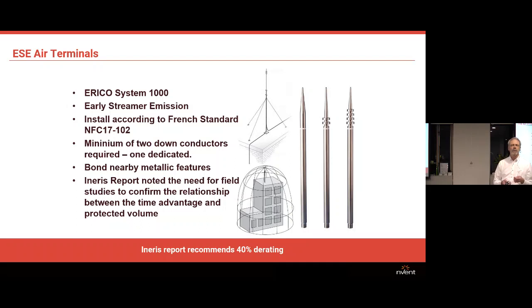But the French government had a lot of these on their building, and they noticed that they were getting bypassed and getting a lot of strikes on their buildings. So they instigated a report called the INERIS report, which found that indeed there were a lot of misses, and this lightning protection method wasn't as reliable as it should be. So they recommended that a proper study be made into reviewing the whole design, and in the interim that the performance of it be downgraded. And on the bottom line in the red bar, you'll see the INERIS report recommends a 40% derating of that standard.